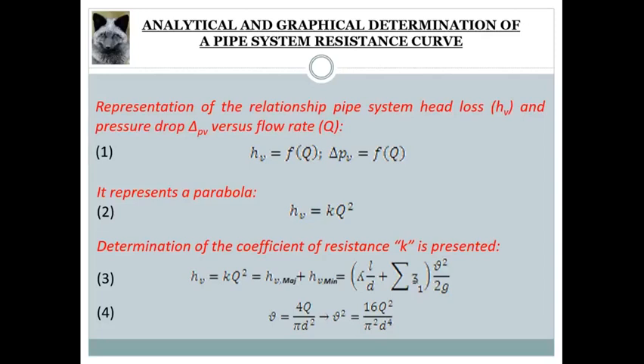The resistance curve of a simple pipe represents the graphical relationship between the head energy loss HV or the pressure drop delta PV and the flow rate Q, which is given in equation 1. The pipe system resistance curve represents a parabola, which can be described by equation 2.